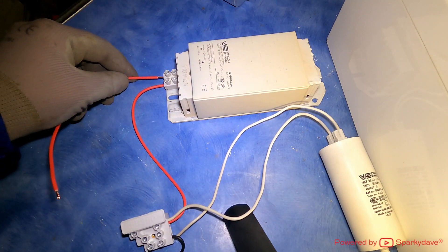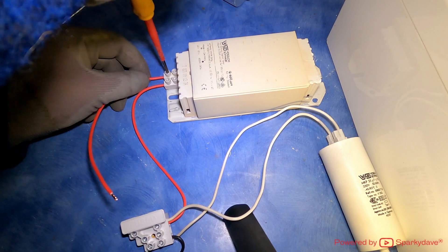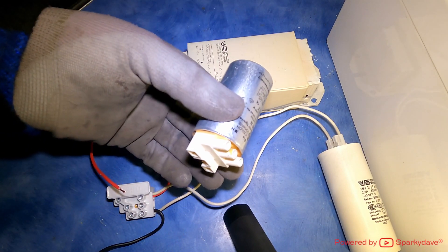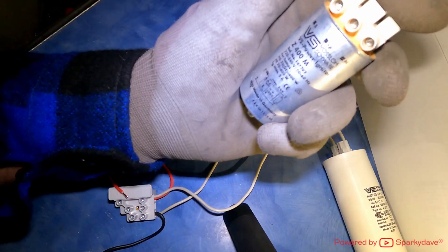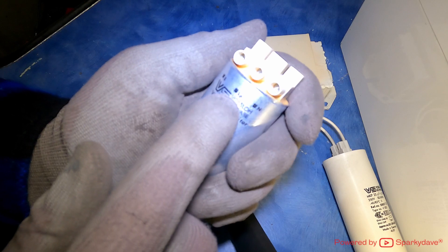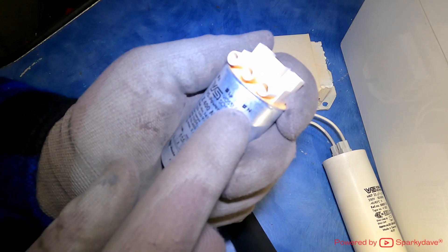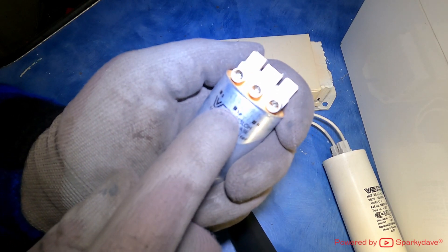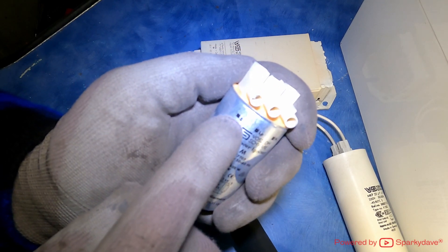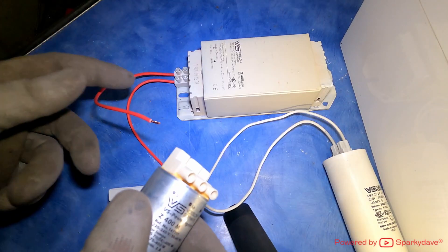Now we're going to have a phase cable coming out of the ballast, and then at this point we're going to connect the igniter into the circuit. On the igniter here you'll see three terminals: a B, an LP, and a N. N is neutral, LP is the output to the lamp, and B is the input from the ballast. So this cable coming out of the ballast will go into the B terminal.